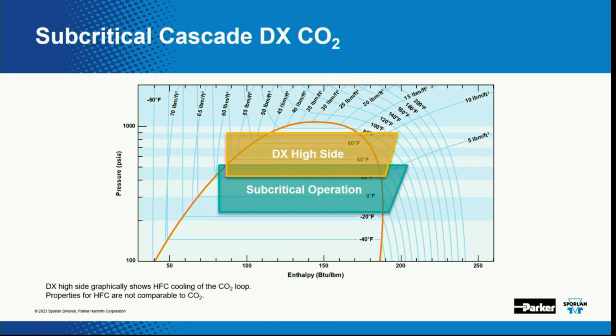But in order to get that CO2 into the subcritical range, we're using an HFC on the chiller plant, if you will. This is a true subcritical system where we're actually expanding the CO2. We're taking liquid CO2 and expanding it, taking it through saturation all the way to a superheated state, and then bringing it back around again. But in order to make that happen, we need the HFC chiller on the high side. I'll show you what that looks like.